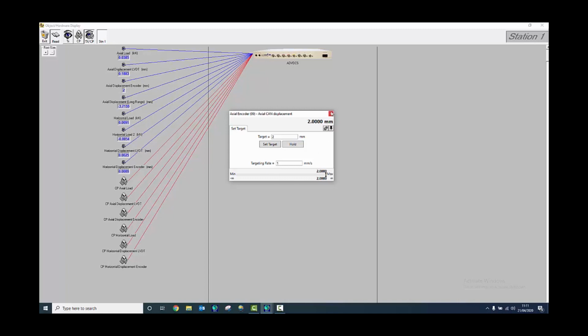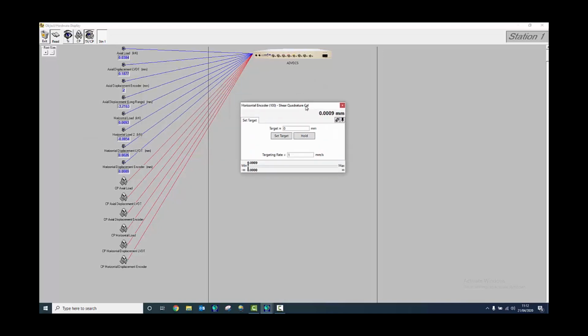So the last thing to check will be the horizontal displacement transducers. So as you can see, we have the LVDT and the motor encoder. So if I select the encoder control for the horizontal axis, I can target 1 millimeter. And as you can see, both of our transducers moved by 1 millimeter into the positive direction. Target 2 millimeters, you can see that both of the transducers moved by 2 millimeters and return back to 0.